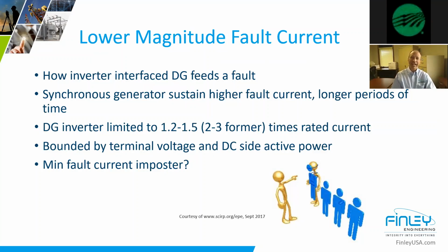Okay, so a couple of points on how a solar inverter is a little different than a traditional induction fed generation source. I want to talk about that for a few minutes. The difference is how they feed the fault, and that's why it's an impact to our systems. A synchronous generator typically has higher fault current magnitudes and longer periods. You have a rotating device that's ramped up and can feed in higher magnitude. It's not as quick to respond if you evaluate at a cycle level.